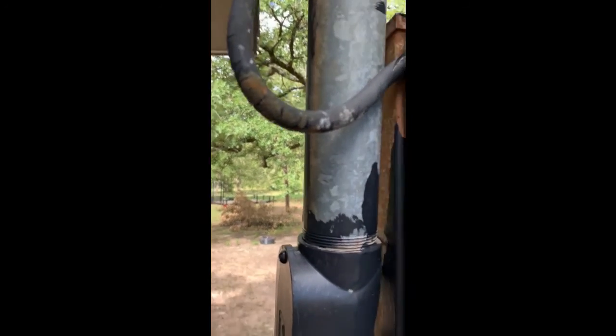I come around the backside. This is a metal pole and I'm going to show you why you shouldn't just reach over and touch a pole before inspecting it. I come around the backside here and you can see that the sheathing has been damaged, but you go up a little bit and you can see where the hot cable is running directly to the metal contact.